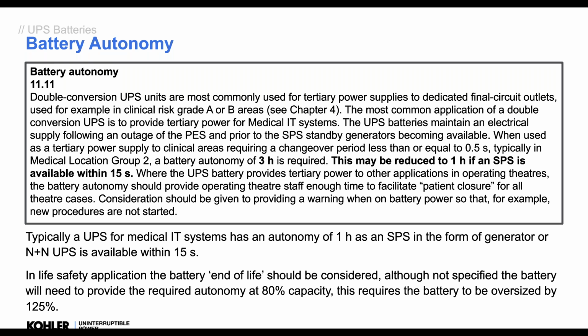One thing that it doesn't talk about in HTM, but it should, is the fact that the battery should be sized for end of life. So if you size a battery for 1 hour at day one, as soon as it starts being used, it's going to age and you won't have an hour available at full load.